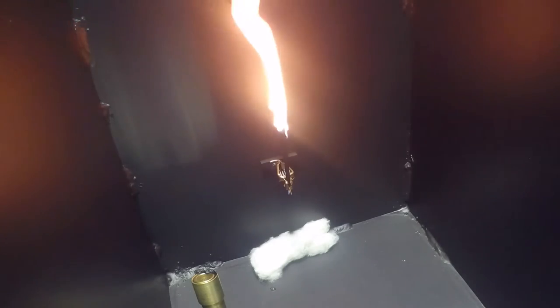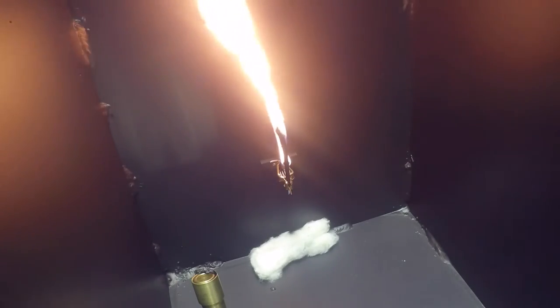As you can see from the first sample, it is coming nowhere close to passing this flame test. The cable jacket is dripping away, which is exposing the cable core and providing more fuel for the fire.